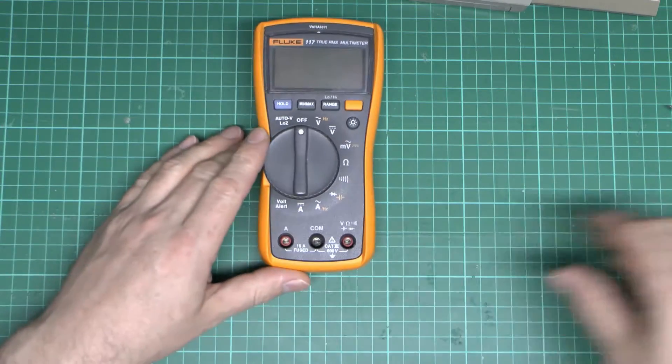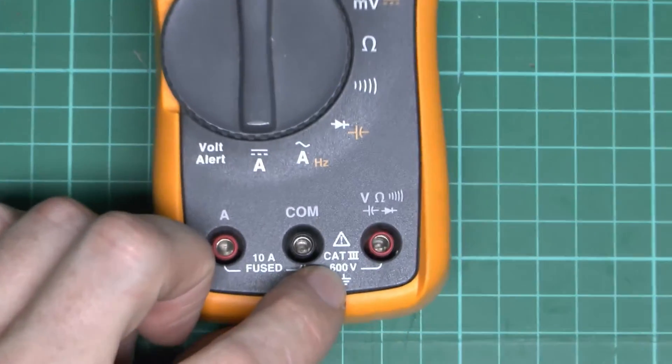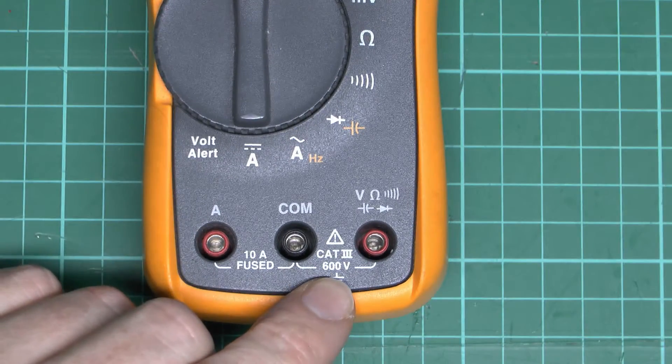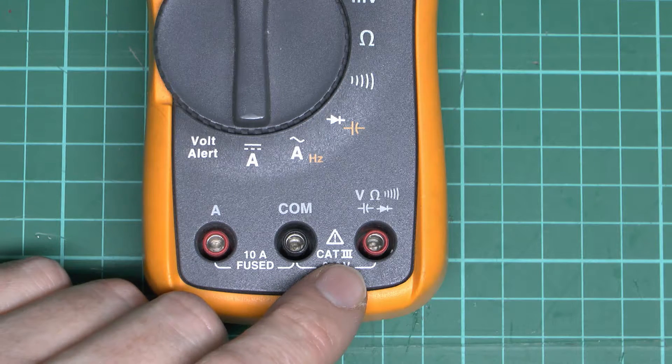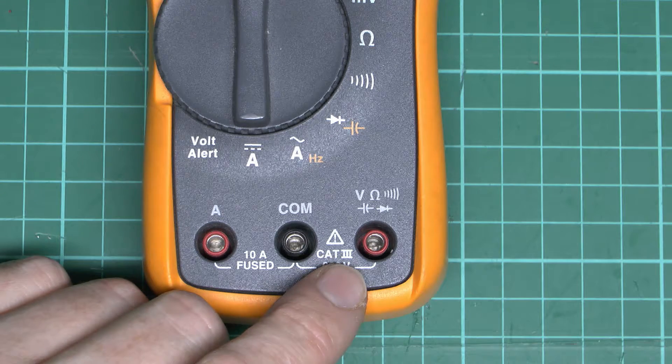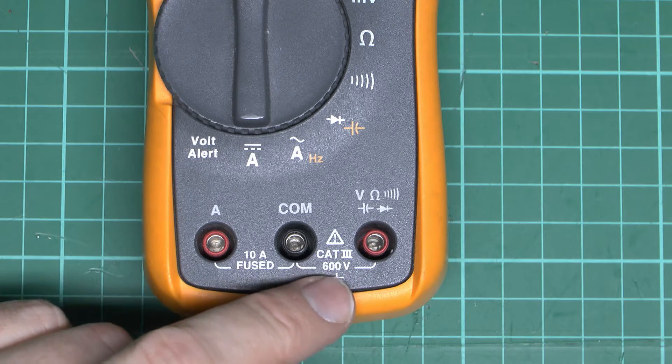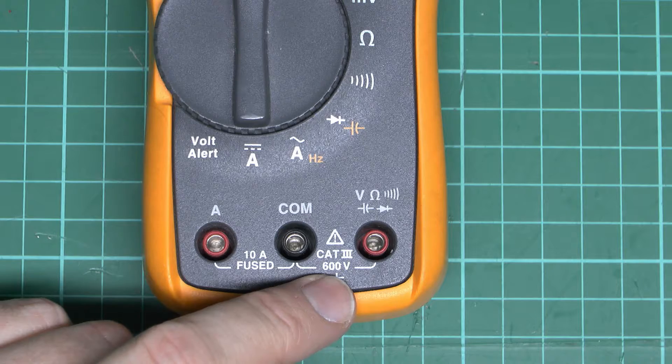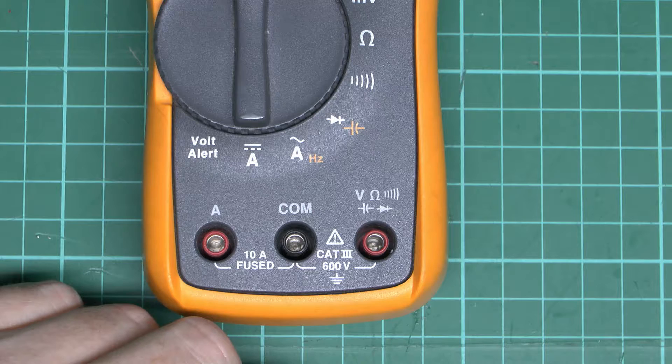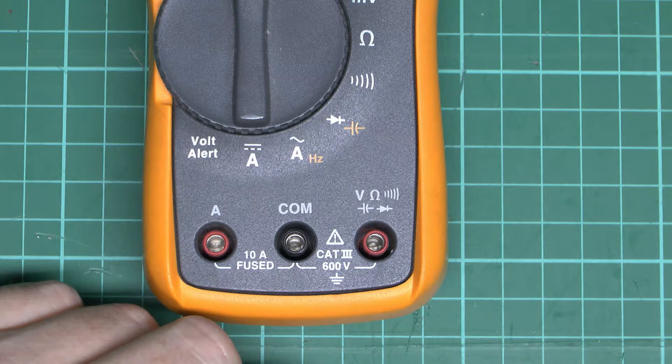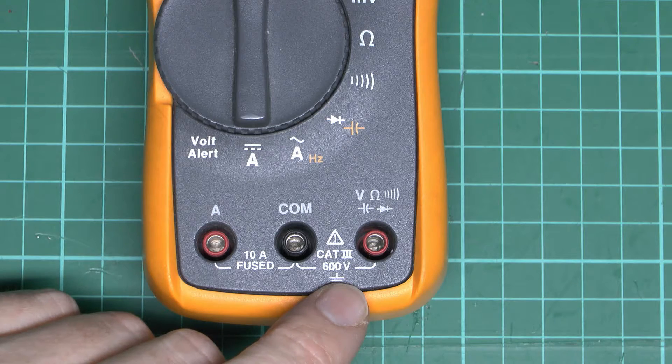Now this particular one here, which happens to be the one with a rating on that I've got, is a category 3 rating, and again it's 600V there. The category refers to the distance that you are from the source of the supply. So the closer you are to the source, the higher the category number you would need. So the highest number is actually a category 4, and that would represent the situation of an entrance to the building where the main power comes in, all the way down to category 1, which is really not intended for connection to the mains at all.